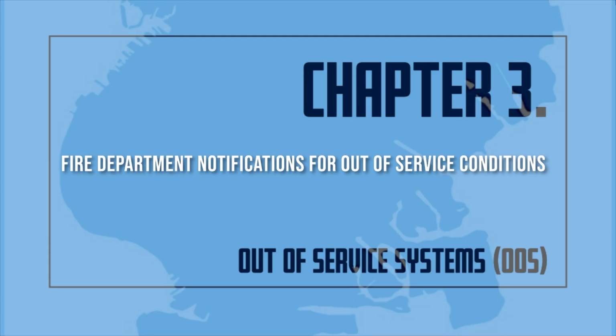5. For planned removal from service, notification must include the date and time the fire protection system will be placed out of service and the estimated duration the system will be out of service. 6. For an unplanned out-of-service condition, notification must include the estimated duration the system will be out of service. 7. The floors or areas in which the fire protection system is out of service. 8. Whether the other fire protection systems are in good working order.